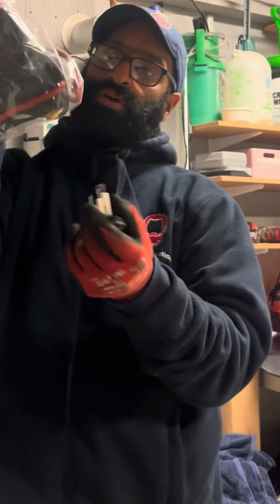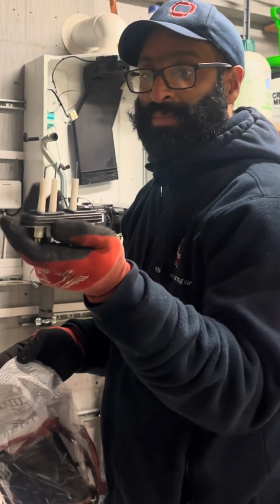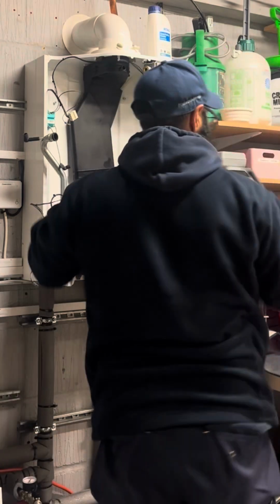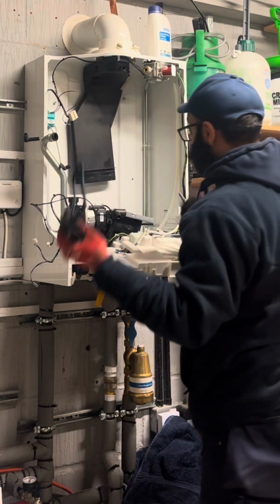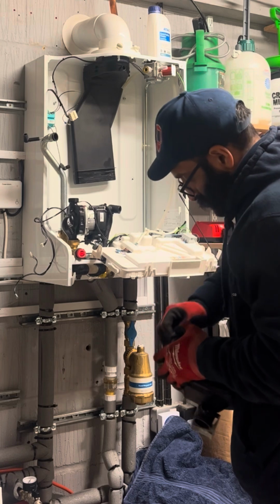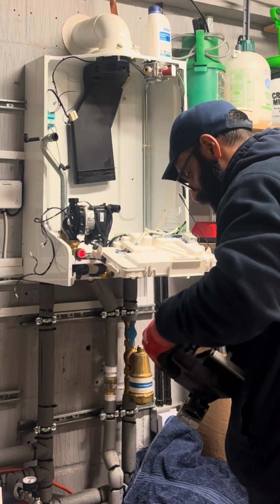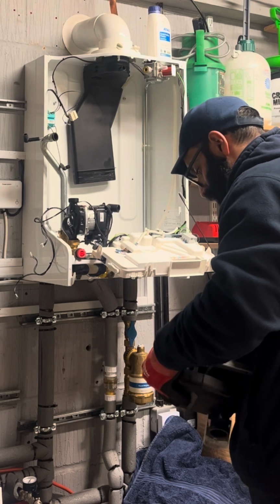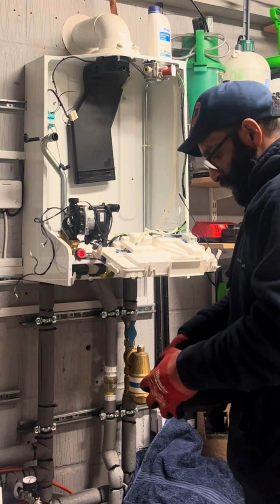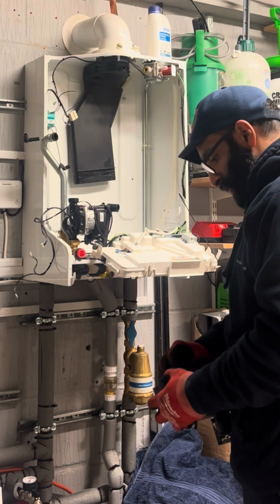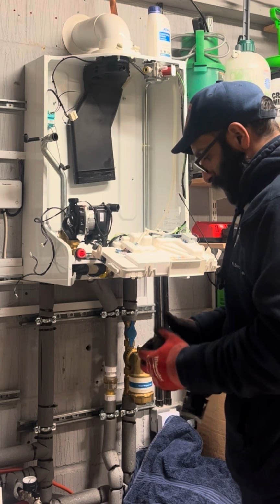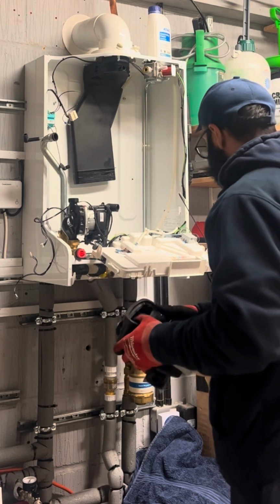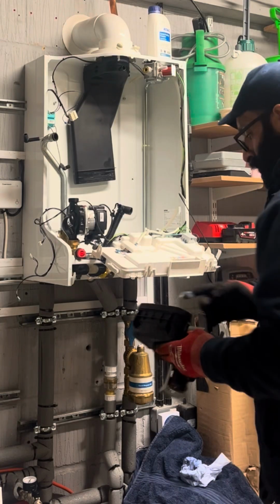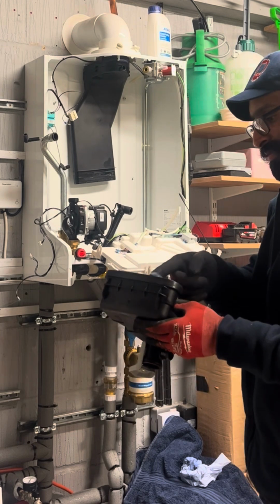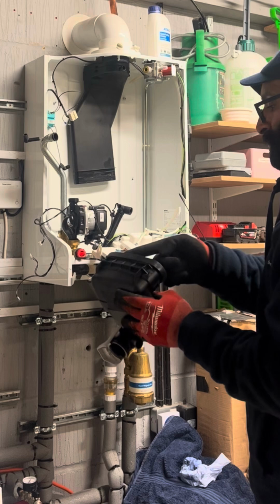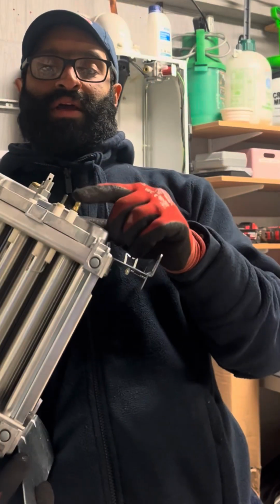So the kit comes with all the seals and the new seal for the electrodes. Clean them up and pop them back in. New seal on the back and new seal on the sump. There we go, that's all done. Just silicone grease on the seals, then the temperature sensor and electrodes.